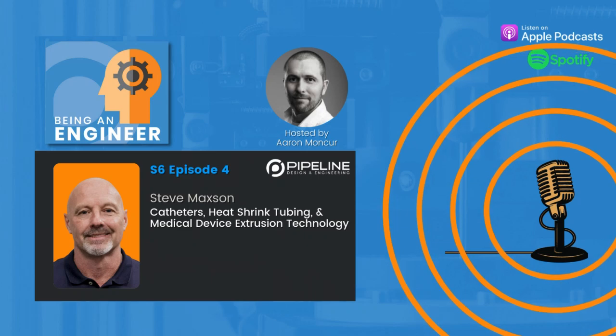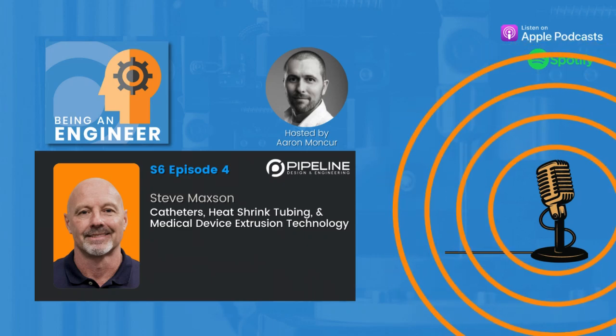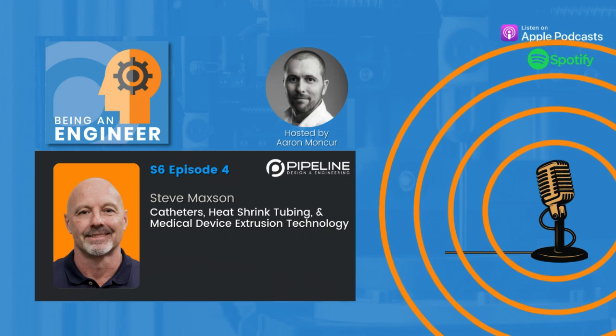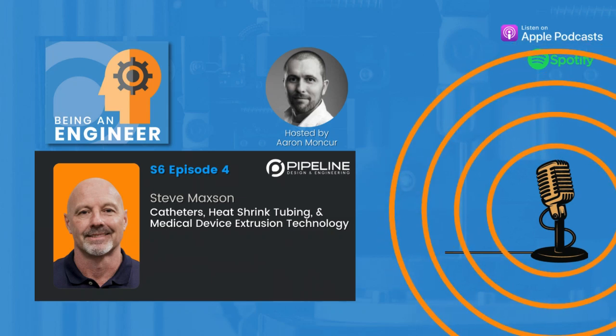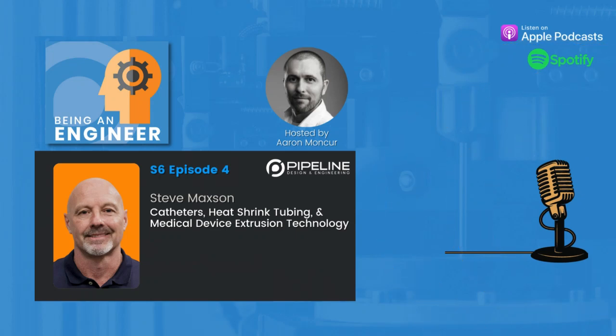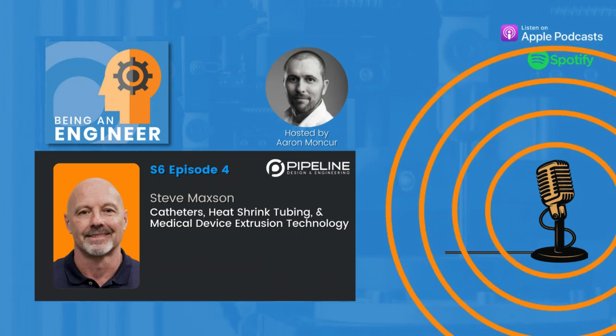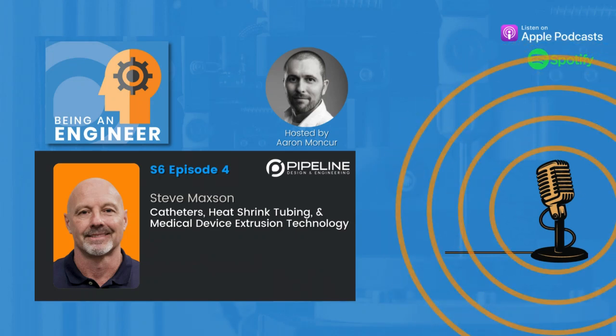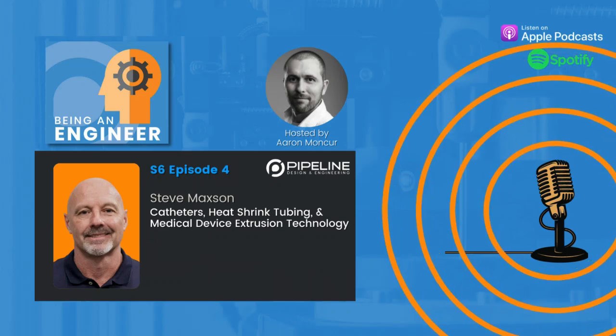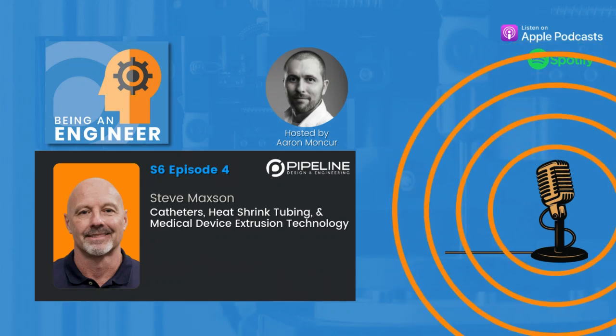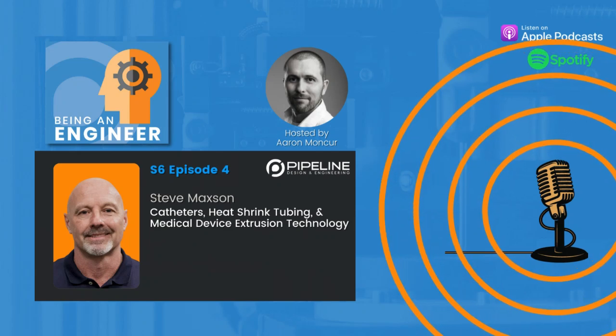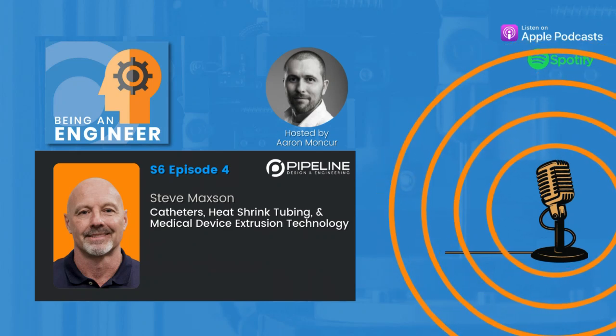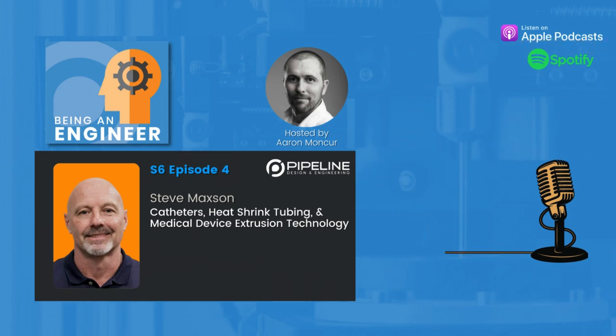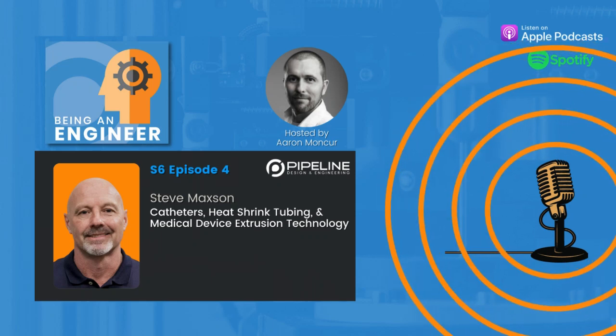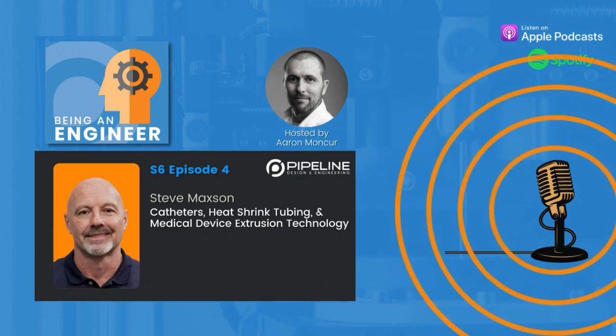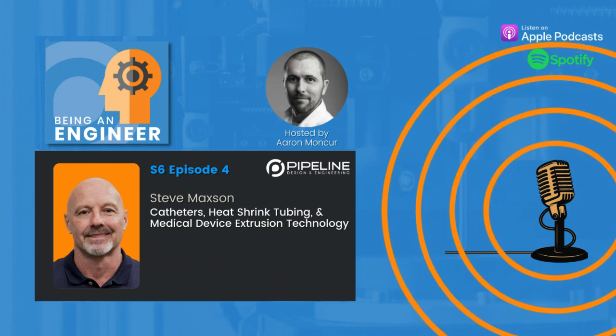We worked on a device a little while ago that was a transseptal needle, I think it was, and it's not really a needle. Those of you in medical devices are probably very familiar with that. But when I first heard of it, I thought we were going to be getting something sharp. Anyway, that wasn't the case. It's just called a transseptal needle. But at the tip, there's an electrode, and it was maybe a 3-foot long, very thin metal shaft, and they used heat shrink to cover the entire shaft except for the very distal tip, where 5 millimeters were exposed as an electrode to do its business inside the body. That was a recent area where I saw heat shrink tubing used in medical devices.